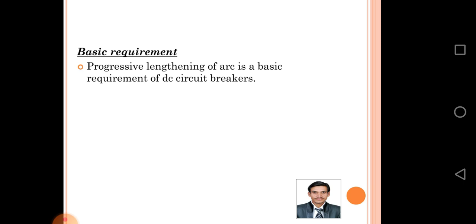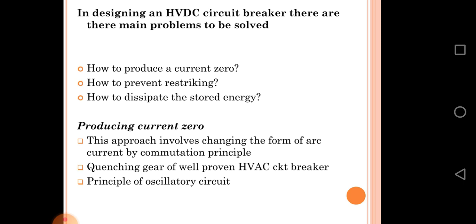In designing an HVDC circuit breaker, there are main problems to be solved: number one, how to produce a current zero; how to prevent restriking; how to dissipate the stored energy. Producing current zero — this approach involves changing the form of arc current by the commutation principle.